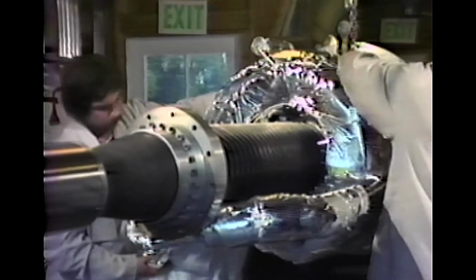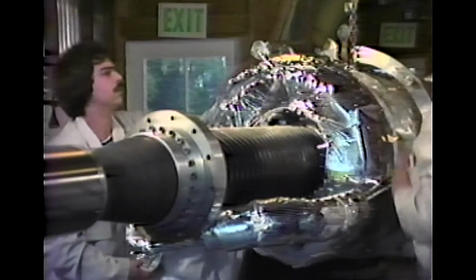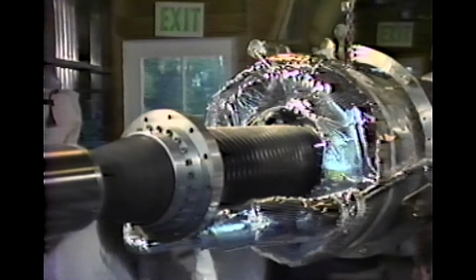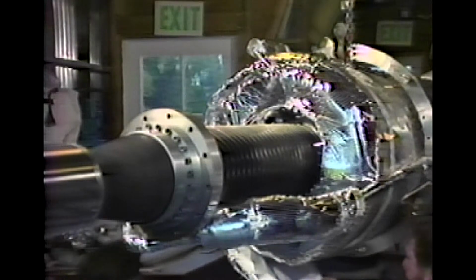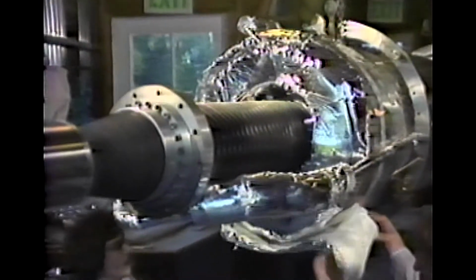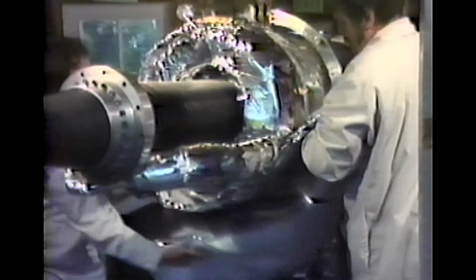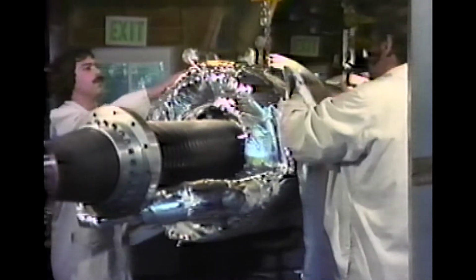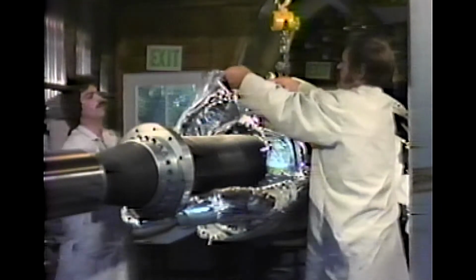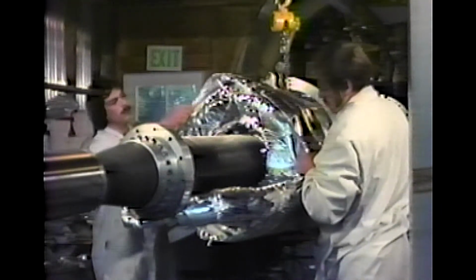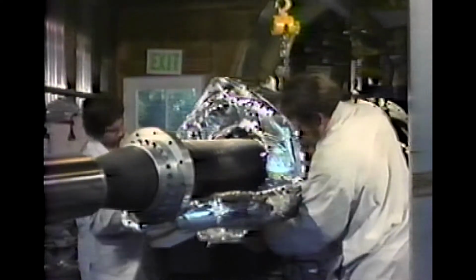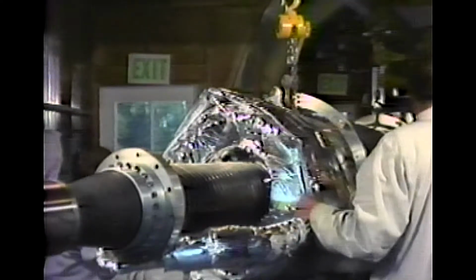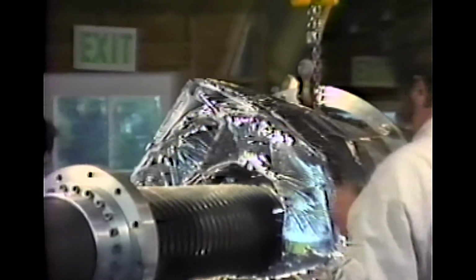The vacuum containment vessel, which is the outside surface of the termination, permits the air to be evacuated from the space containing the super insulation blanket. Once the air has been removed, heat can no longer penetrate to the interior surfaces by means of convection. The vacuum space of the cable enclosure pipe seen earlier is permanent and does not require pumping. However, due to the large number of joints and the need to disassemble the terminations on occasions, the vacuum in this part is maintained by the continuous operation of pumps.